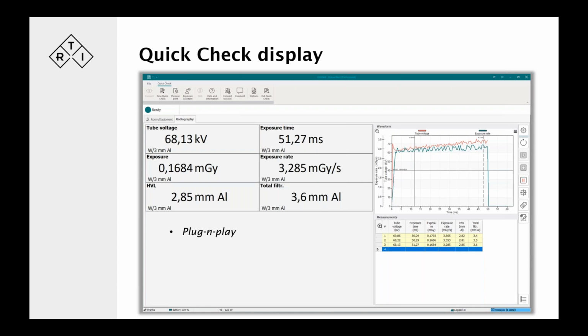It has plug-and-play functionality, so that when you plug in the probe or change the configuration of the unit, it follows and asks you what you want to do. If you attach a dose probe, for instance, it will ask you, do you want to use both probes or just one or the other? So that you need to decide how to use that software. It is Windows-based. That means that the field engineer or the biomed tech can run it on the laptop, which most of them carry anyway. So there's less to carry around, and the data is then stored locally.